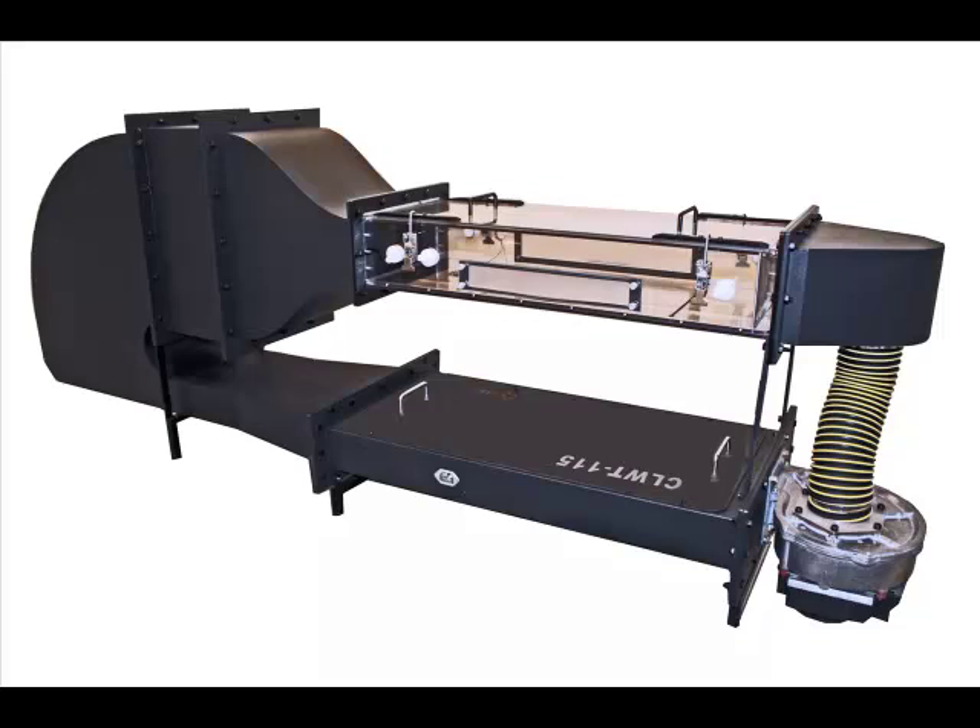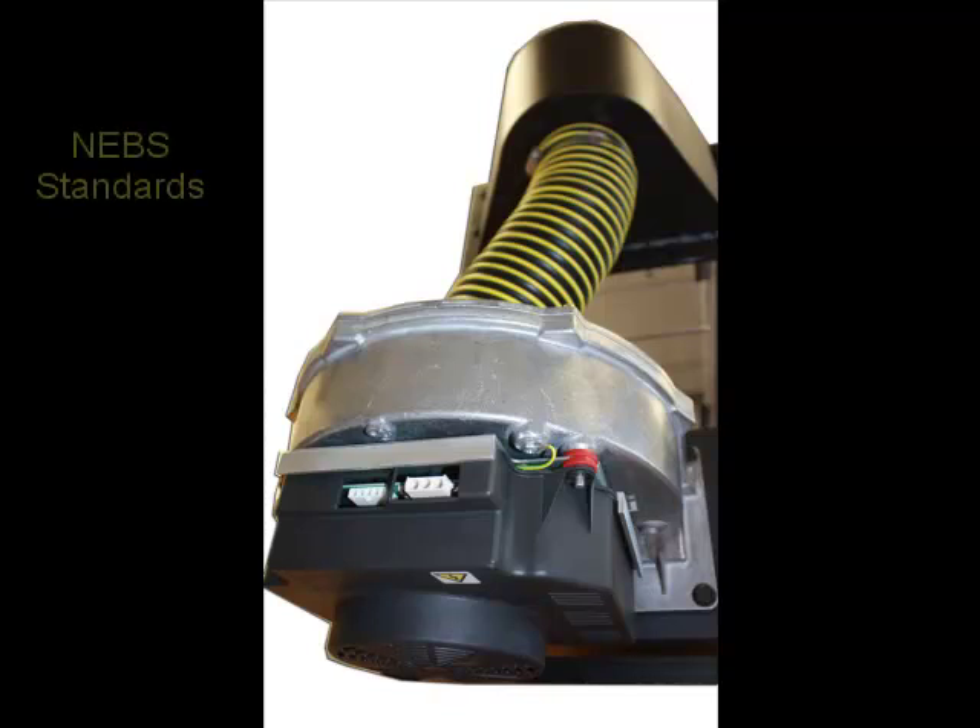Manufacturers need to know how their device will work at these high temperatures. The testing of boards and components in hot air is a requirement in some NEBS and other testing standards. The precise control and temperature range of the CLWT-115 wind tunnel will accurately evaluate the effects that these high temperatures will have on a component's response and reliability.